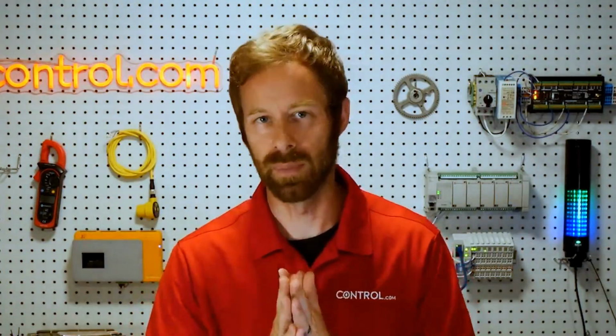So again, depending on the carrier that's in play, the Modbus commands, which do not change, can be wrapped into a data packet to be sent over Modbus TCP or Modbus RTU or Modbus ASCII format. A lot of controllers with multiple communication headers can accomplish any of these communications.